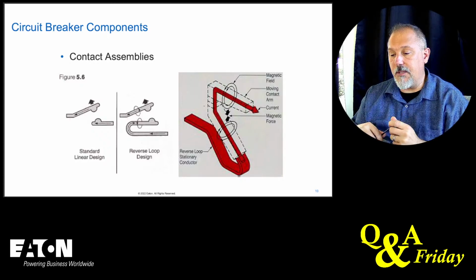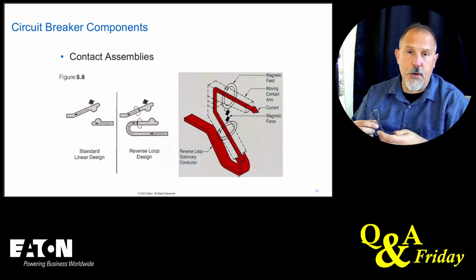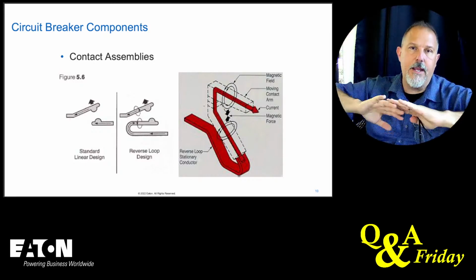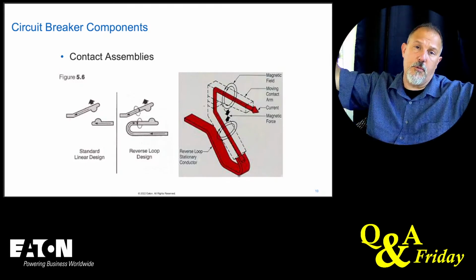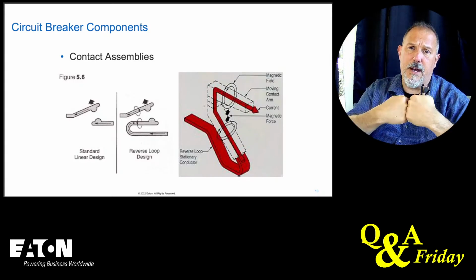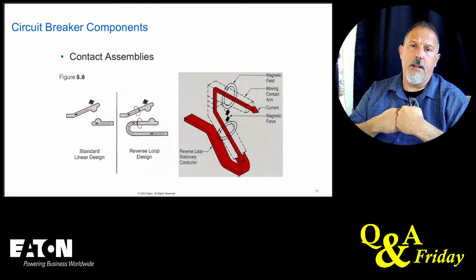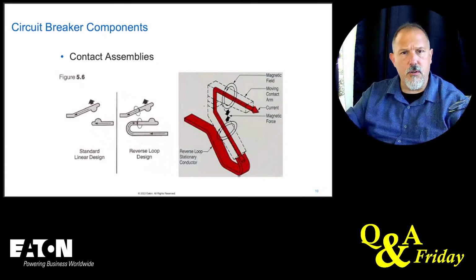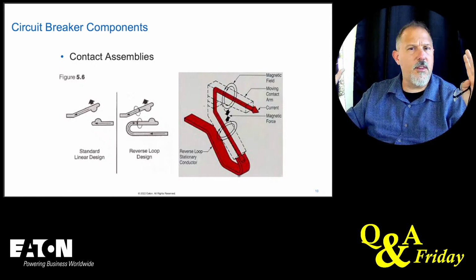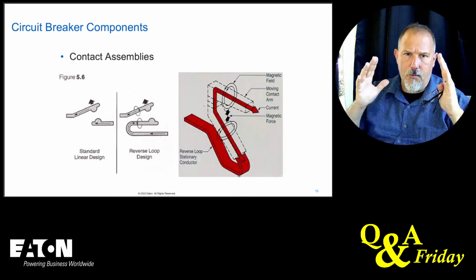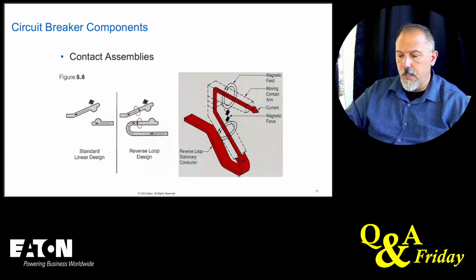Do we use that same technology in other breakers? Sure, we could, yes, but I'm not being current limiting. Again, as I get further up in the power distribution system, I'm more concerned about not tripping on these high fault currents due to multiple inrush currents, multiple motor starting currents, and things of that nature. I want to let that system start. So, let's take a look at those trip curves, right?